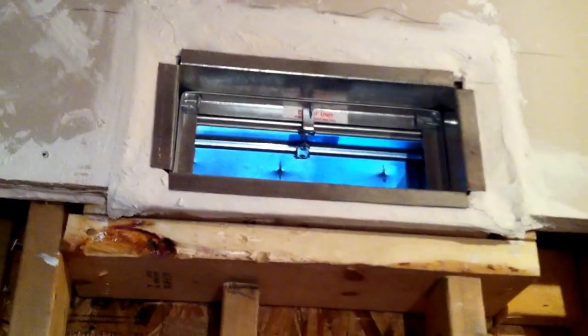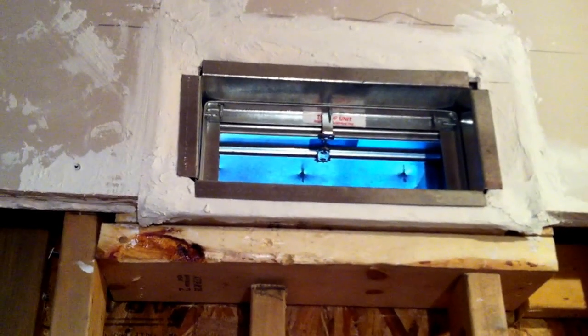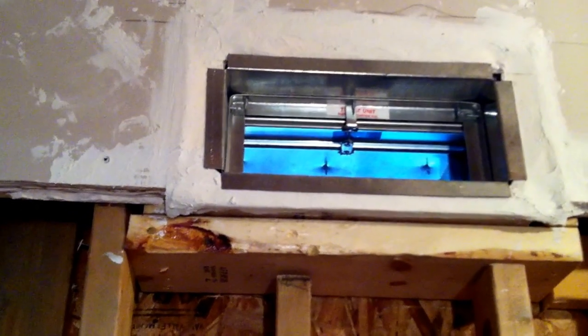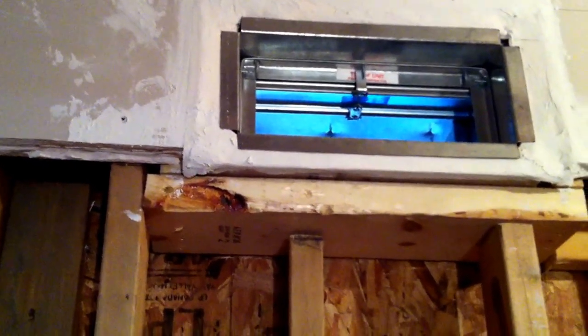The other thing people often ask is — it's open normally, but in the case of a fire, all of these, as part of the fire protection system, have a damper with a fusible disconnect. If fire is sensed, that fuse is released and the damper shuts to prevent any smoke and fire from entering into a suite.